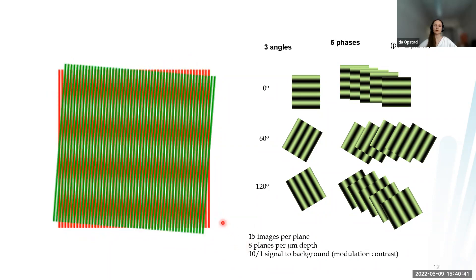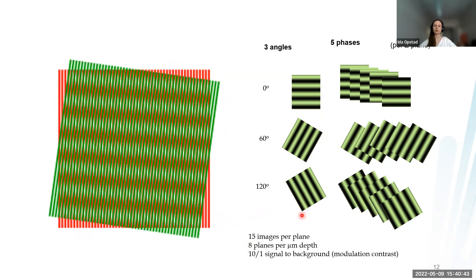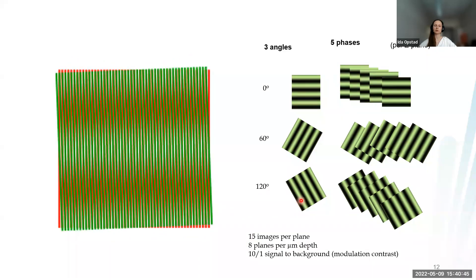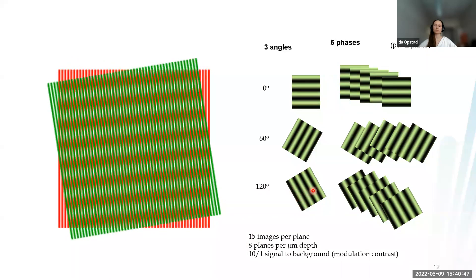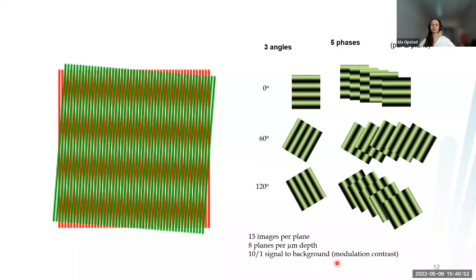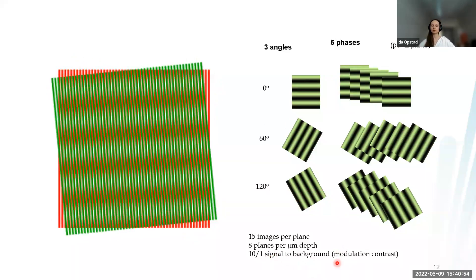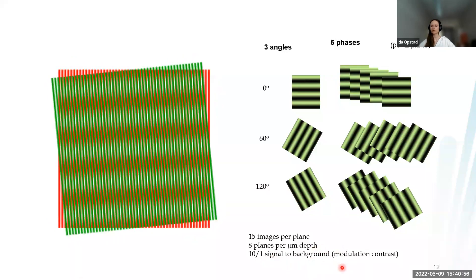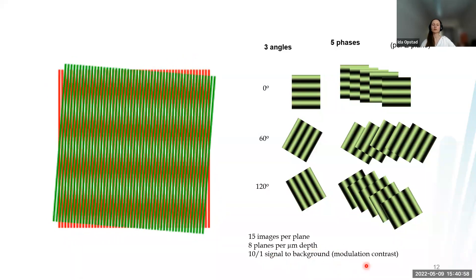For the algorithm to work, there needs to be good contrast of these stripes. They need to be bright enough. We need 10 to 1 signal background ratio approximately and good modulation contrast.